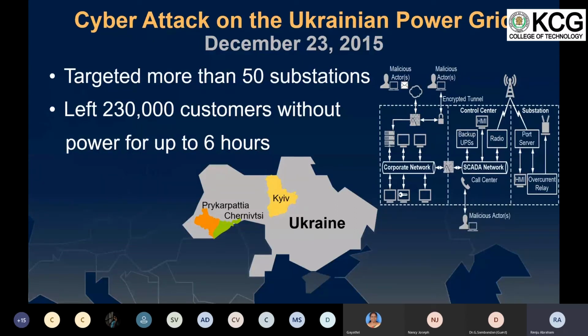In this case the system was directly connected to the internet. The substation was actually connected to the corporate network, which was connected to the internet, and the attackers were able to access the SCADA network. In 2017, hackers gained access to a transmission substation in Ukraine again, and they opened the breaker for the transmission line circuit, which again caused an outage.